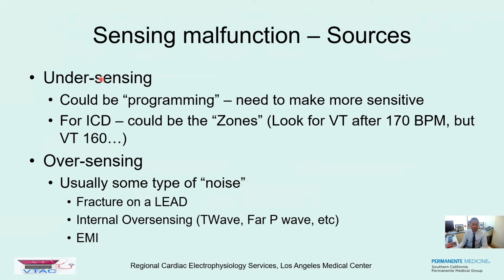So if you are undersensing, you might have to just change the programming with a programmer. You need to make the device more sensitive - you need to change what we call the sensitivity of the R waves so it can see smaller signals. For an ICD, it could also mean the reason it's not treating VT is that the VT is 150 beats a minute, but I programmed the VT zone at 170. So you need to change the zone.